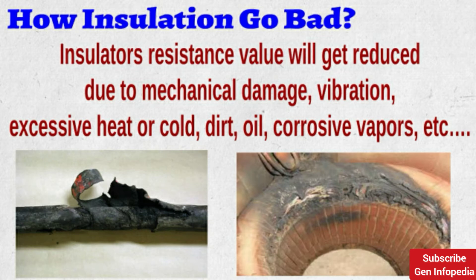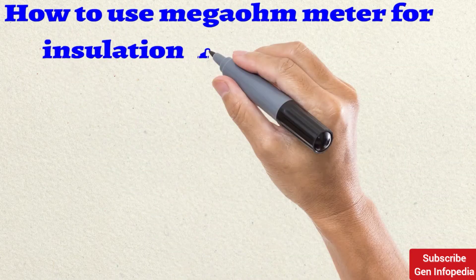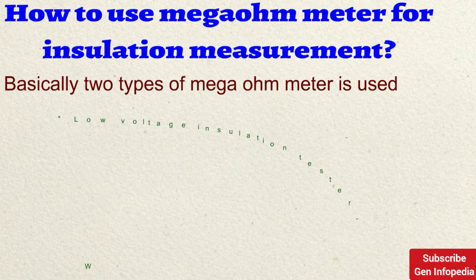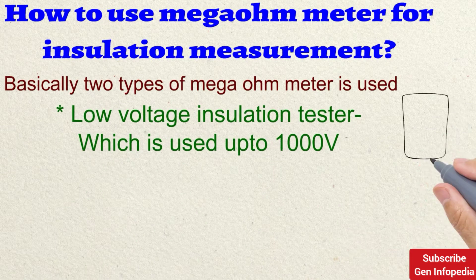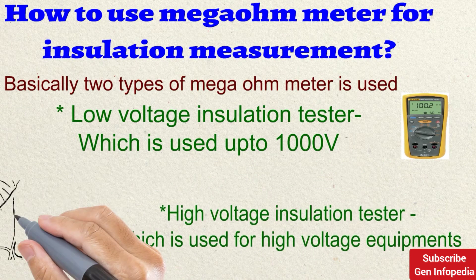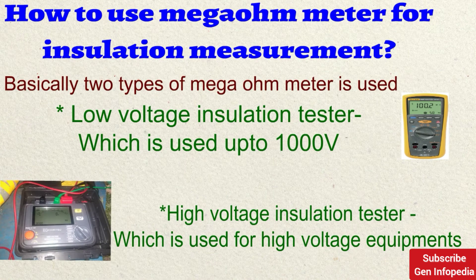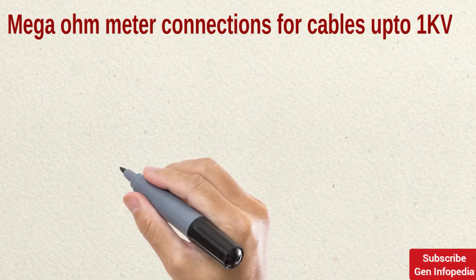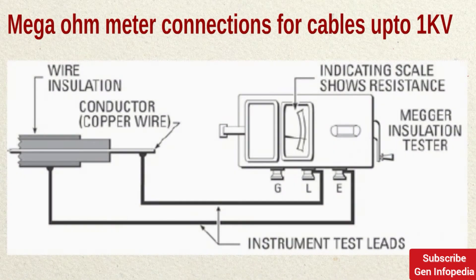Now we will see how to use a megaohmmeter for insulation measurement. Basically two types are used: a low voltage insulation tester used up to 1000 V, and a high voltage insulation tester for high voltage equipment. For cables up to 1 kV, we use only two probes — a line probe and an earth probe. The line probe is directly connected to the cable conductor.